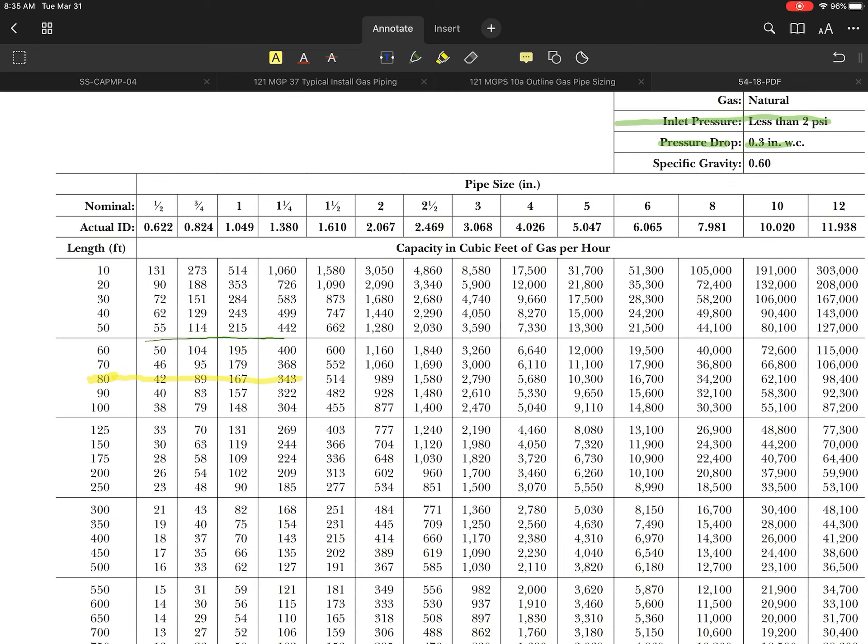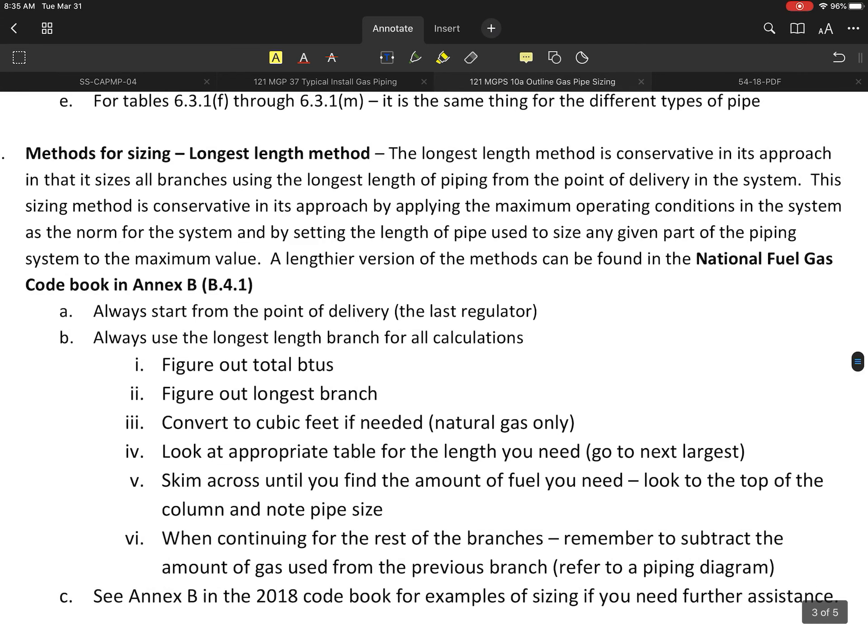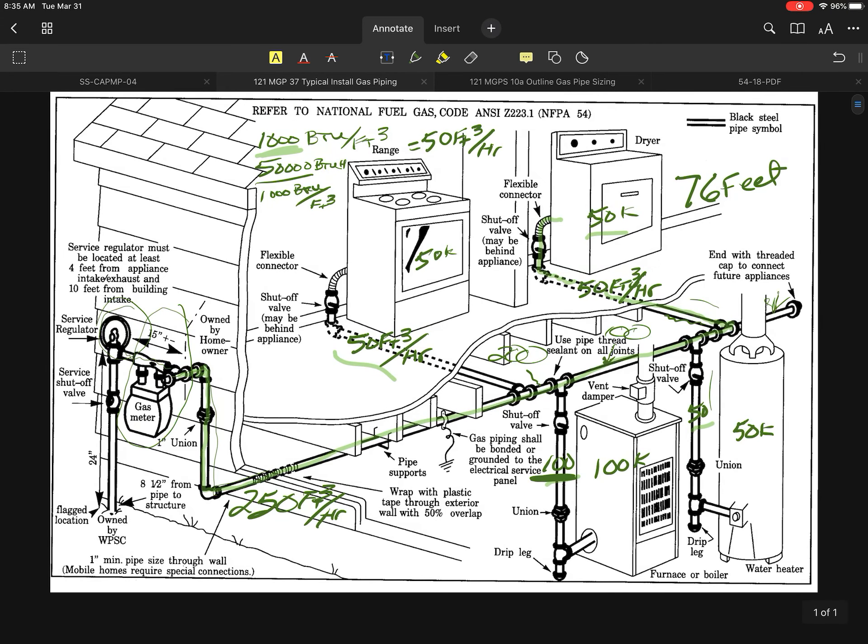I had 250 cubic feet of fuel that I had to run down this system. The 250 cubic feet of fuel per hour at a length of 76 feet using the 80 foot row tells me my initial gas pipe going into that building is going to have to be 1.25 inch, because the 1 inch line would only give you 167 cubic feet of fuel and I need 250. We're definitely going to need to go with the bigger size.